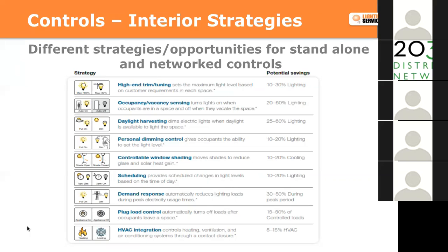HVAC integration is very common, and this is something we've actually been doing for years. We have a motion control in a classroom or an office with an extra contact on it. It can be tied into the HVAC system to open or close, or send a signal back to the mechanical control system to open or close a VAV box to adjust the temperature in a room. Some of these strategies, like tying it into the HVAC system, can be done with basic sensors, while others take a more robust connected system.